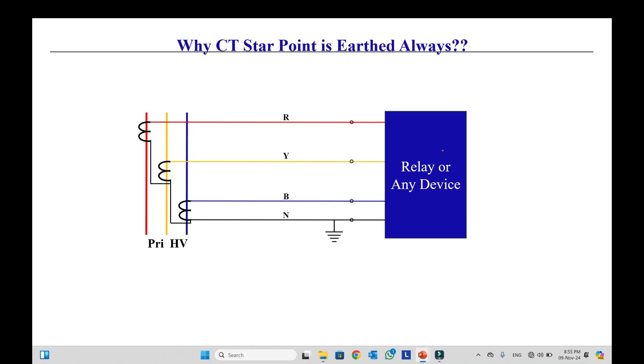Before answering this question, we have to understand the CT circuit. Usually the CT circuit looks like this. This is a very simple case I made for understanding. We have red phase, yellow phase, and blue phase CTs. These CTs are connected in star. So this is our star point and it's neutral. So we have red phase, yellow phase, and blue phase going to our relay.